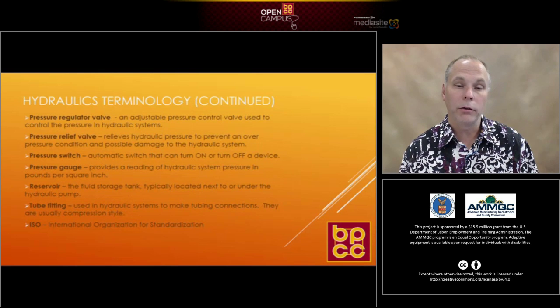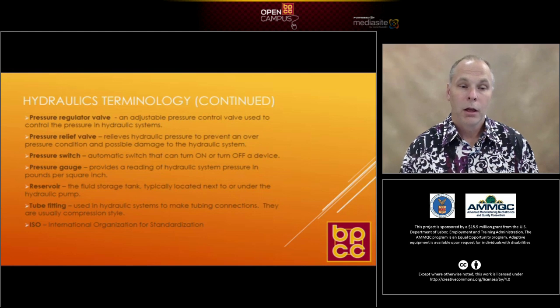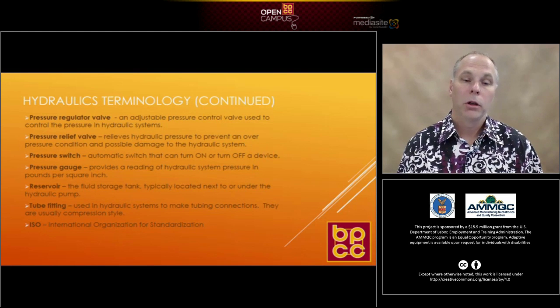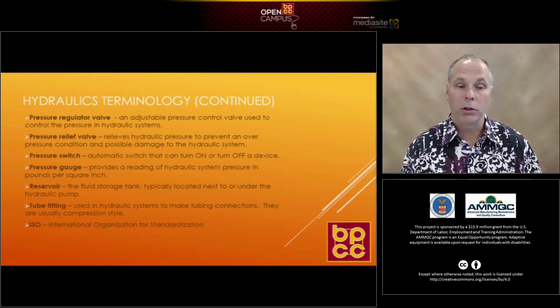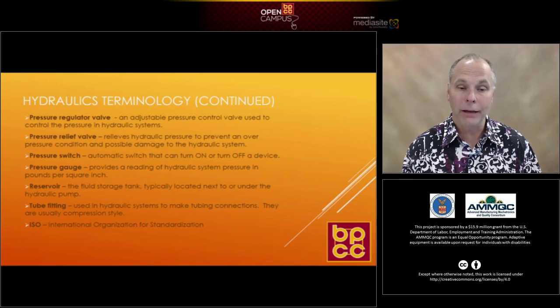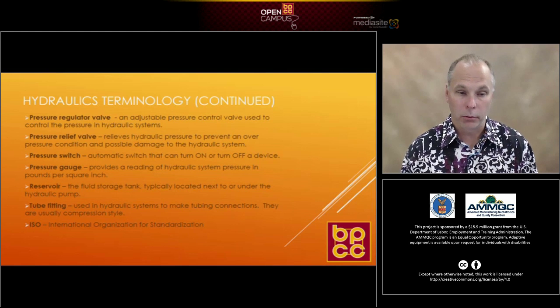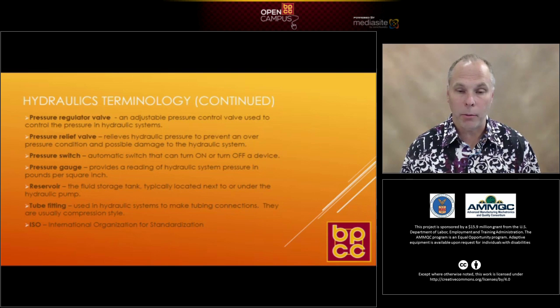A pressure regulator valve is an adjustable pressure valve used to control the pressure of a hydraulic system. These are normally closer to your pumps. Your pump may be able to produce more pressure, but you only want so much used in the system. If the pressure does exceed that amount, a pressure relief valve discharges and releases that pressure before it's passed through the system. Your pump may also have a pressure switch to help keep you within certain parameters.